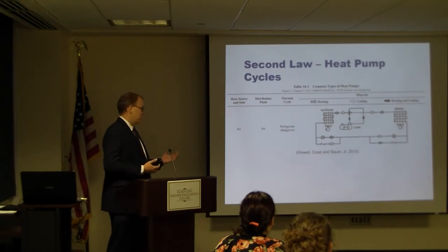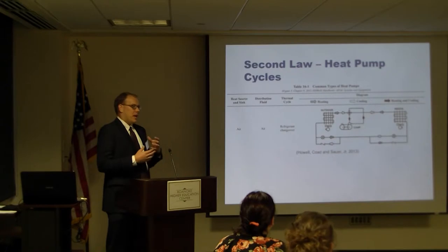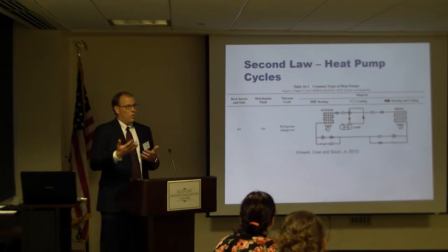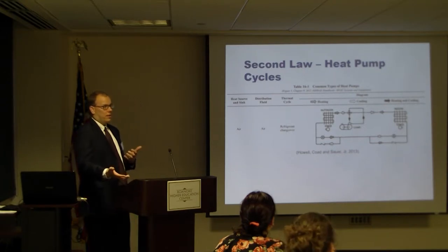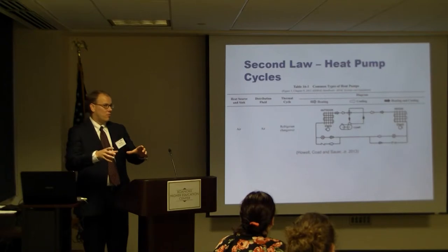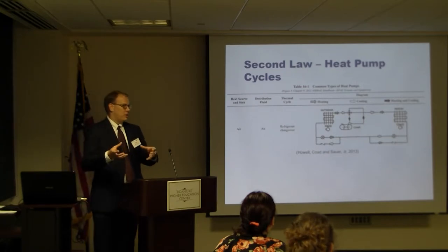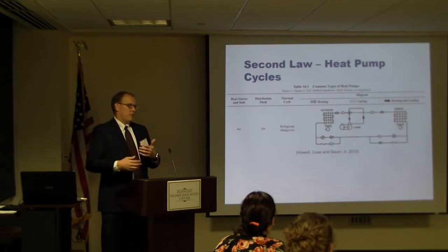We have to find supplemental means to do this. So one of the things we have to do with a geothermal heat pump, or any kind of water-based heat pump, is manage the temperature of that water. In the case of a geothermal system, we look at whether the well field is balanced. Do we have enough heat going in during the summer, so we charge it up nice and warm and store a lot of summer energy in the earth? And in the winter, we come back and extract all of that heat energy we rejected to it in the middle of summer, where we need it to heat ourselves. And we reverse the whole thing.